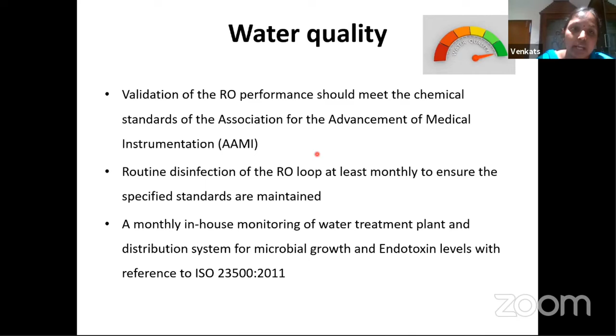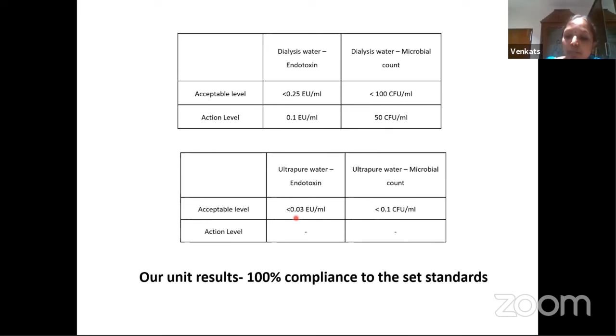These are the acceptable levels. If we are doing standard hemodialysis, the acceptable level for microbial count is less than 100 CFU. Acceptable level for endotoxin count is 0.25. And if we are using ultrapure water, in case we are doing online HDF, the standards require ultrapure water. The microbial count should be less than 0.1 CFU and endotoxin count should be less than 0.03 EU per ml. As per our unit results, we have 100% compliance to these set standards.